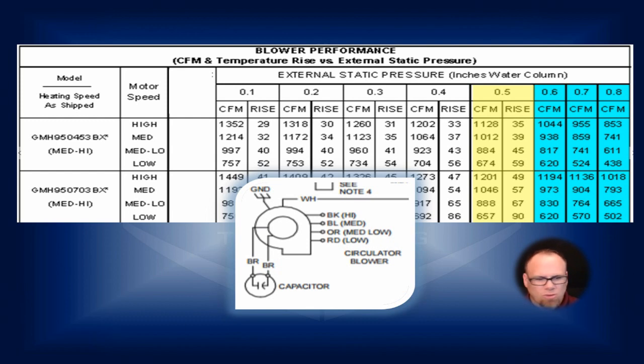Well, you start putting more restrictive stuff in there, then it starts to cut into your airflow and mess everything up. So we can control the filter. We can control the filter both in size and restriction. We can control the return air drop. One of the biggest things that I see as an issue in our industry are the return air drops. 20 years ago, one of the more common filter sizes was a 16 by 20.